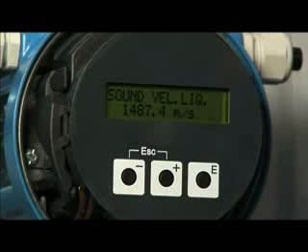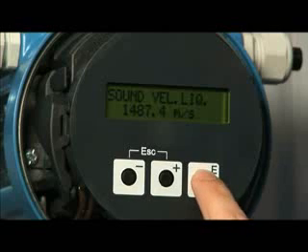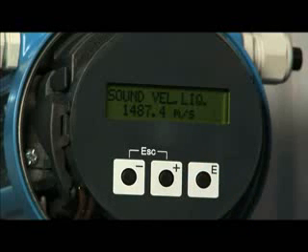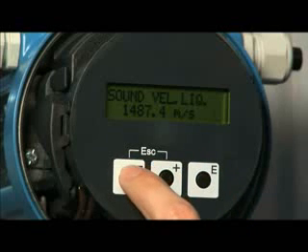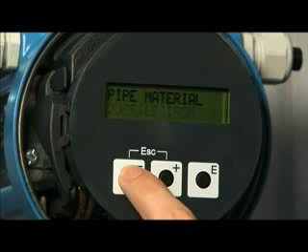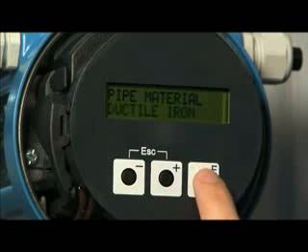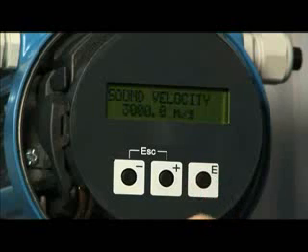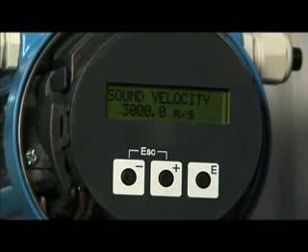The sound velocity of the liquid is then displayed for the normal operating temperature. If you have chosen Others earlier, you will need to enter the liquid sound velocity. The material of the pipe in which the liquid is being conveyed should then be entered. Select the appropriate material. The sound velocity of the pipe is then displayed.